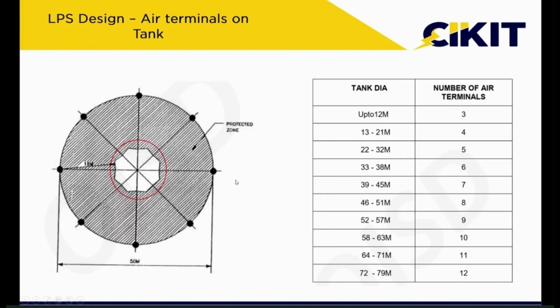So if we are going for this particular methodology, then the radius of protection will be around 15 to 18 meters. If the diameter is 50 meters, then there will be some portion in the center that will still be uncovered. So if we are going for 50 meters and placing the air terminals along the perimeter, then the center portion of the tank is still unprotected. That is one of the drawbacks of this particular methodology.